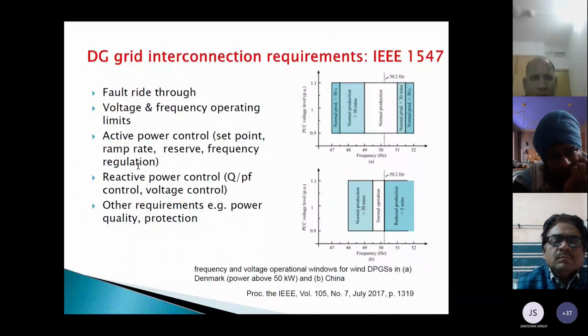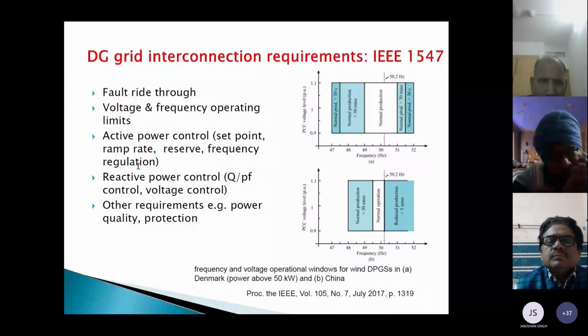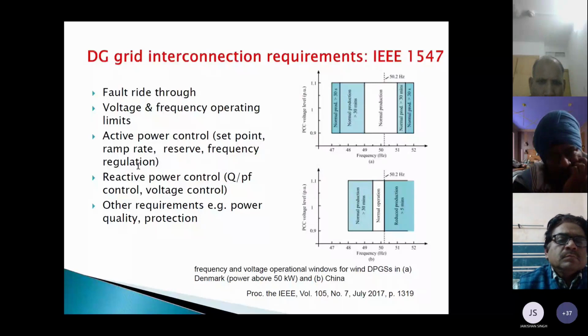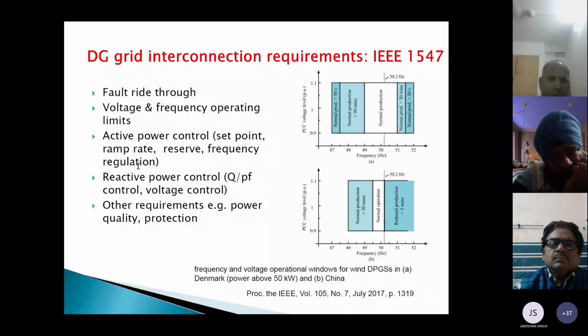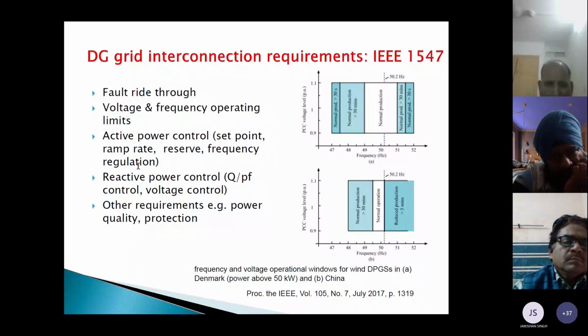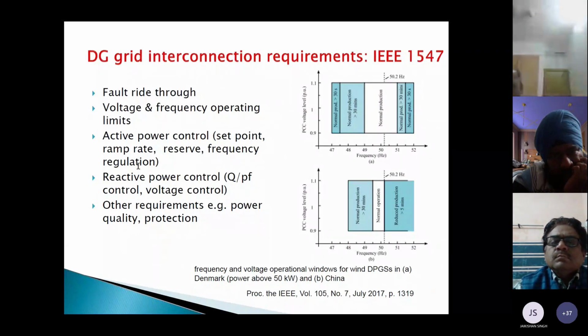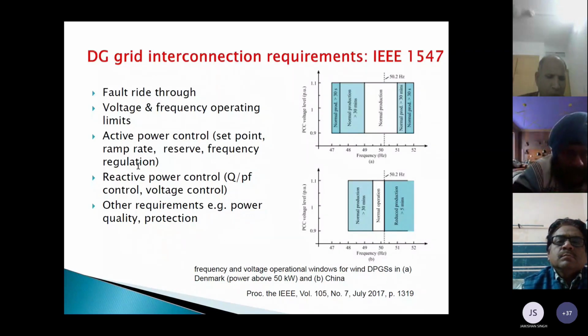When we are integrating distributed generation to the grid, there are several interconnection requirements covered in IEEE standard 1547. These interconnection requirements include fault ride-through capability, voltage and frequency operating limits, active power control in terms of set point, ramp rate, reserve requirement, frequency regulation, reactive power control, voltage control, and other requirements in terms of power quality, protection, etc. This topic itself is so detailed that it needs a separate session to discuss in detail. So I will briefly explain some aspects of these distributed generation interconnection requirements.